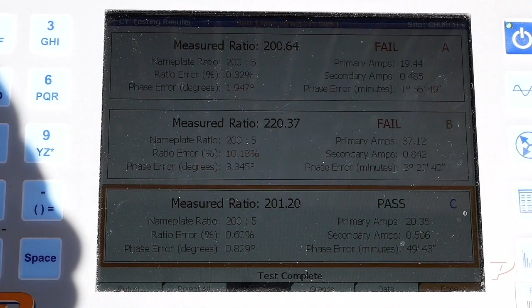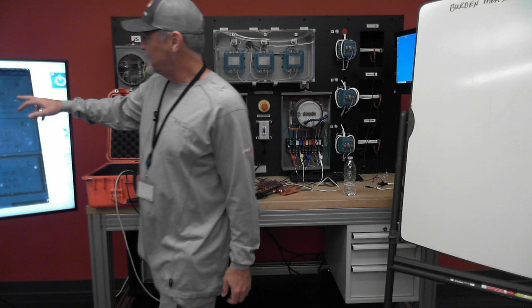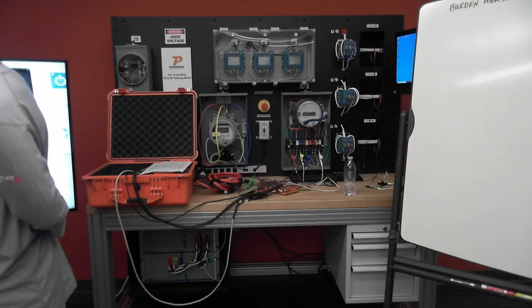So what we've got... okay, so not what you would really want to see when you run the test, right? You can see we got a fail on A phase, and we follow the red to see why we got the fails. So we have a fail on A phase right here, and it looks like the fail is because of a phase angle error.